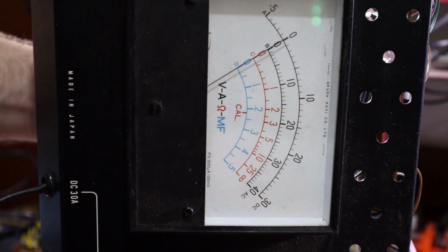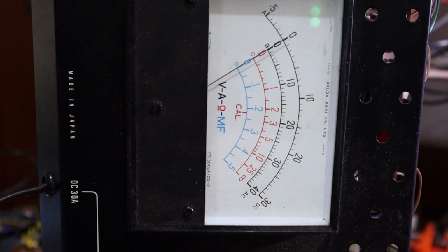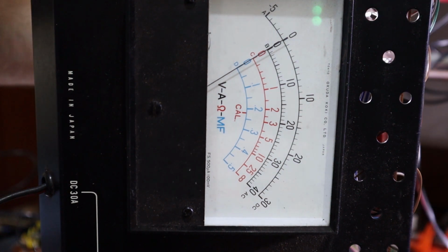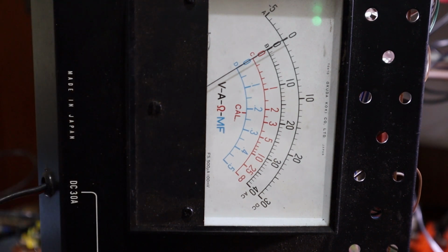It's possible that maybe when that fault current melted the ground wire, it actually backfed through the meter and burnt the coil on it. So I think we're probably at a loss to fix the meter side of it.